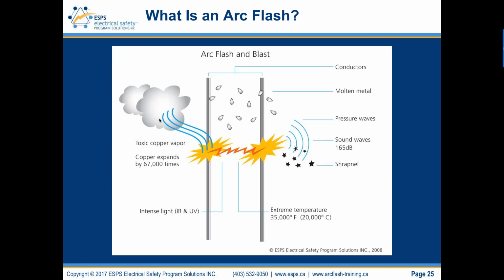So there's just a visual graphic of an arc flash. Again, we compromise the gap between conductors. We get an arcing fault, ionization of air. We get a resulting arc flash, and there's heat that's released. The point of the arc is 20,000 degrees Celsius or 35,000 degrees Fahrenheit. We get blast pressure. I'm not going to say we don't get blast pressure, but there's blast pressure. And that blast pressure comes with a noise. So we get sound waves, instantaneous, possibly up to 165 dB.